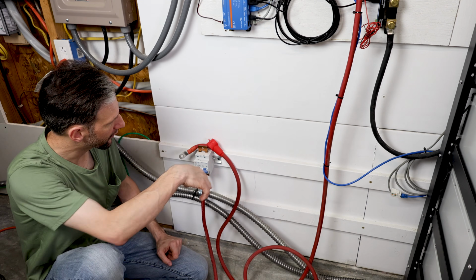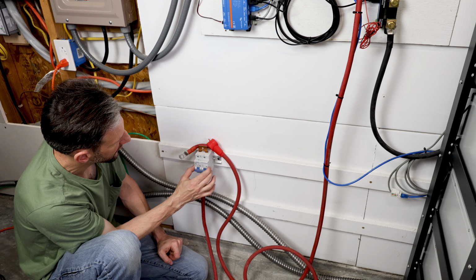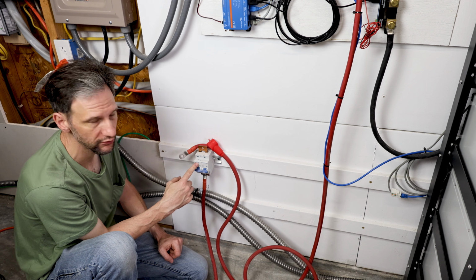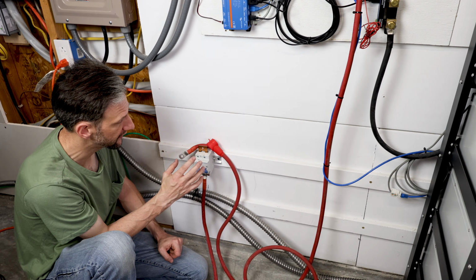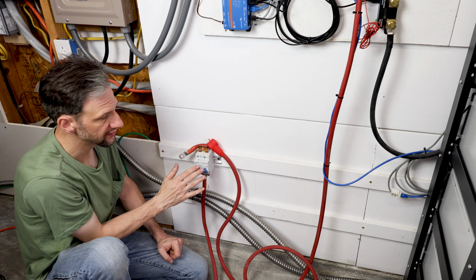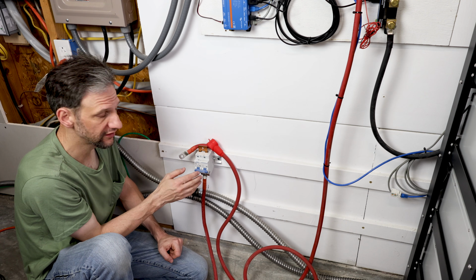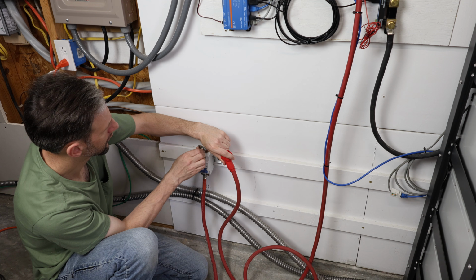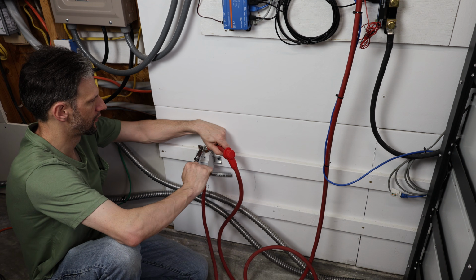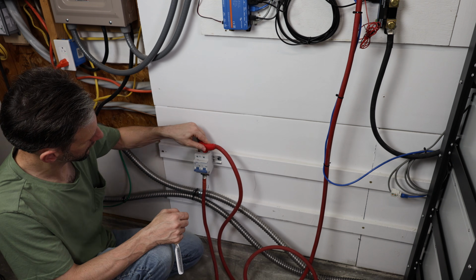Since the battery doesn't have a breaker, I'm going to use this breaker in a double configuration, which will allow me to have a 200 amp limit for my connection and be able to quickly and easily disconnect the battery. It also gives me a little bit more overcurrent protection. I'm using 2-aught cables since we'll be pulling up to 200 amps.